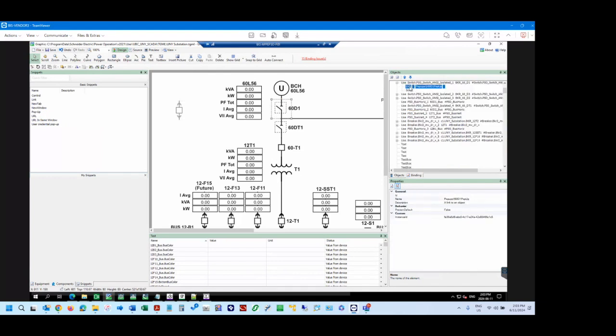Here, the link is literally defined as where you are in the structure of your TGML folder. So I'm already started in the TGML folder. What's the subfolder? The subfolder is called pop-ups / and then the name of the pop-up. Not even a .tgml, just leave it like that. So that's going to go into the pop-ups folder and find me the exclamation point 60D1 pop-up.